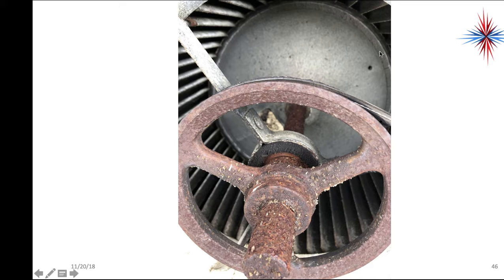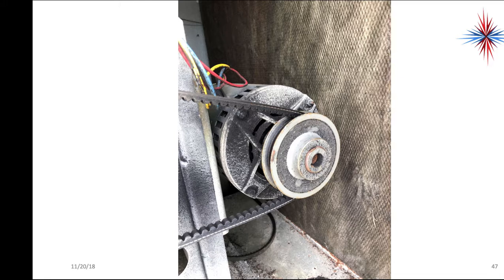So I'm noticing that we have really badly rusted and dry bearings here. Okay, so we'll go further. I see a lot of belt debris around this motor. This whole motor area has belt debris. Believe it or not, if a belt is getting that hot and throwing that much stuff around, especially if the blower motor or the blower wheel bearings have gone bad, this will actually appear as smoke in the ductwork because that smoke will be blowing around.